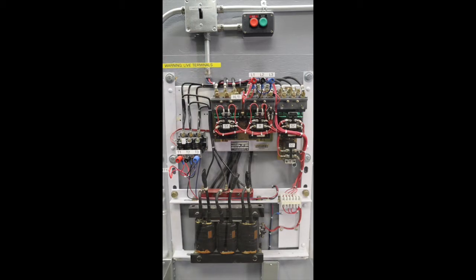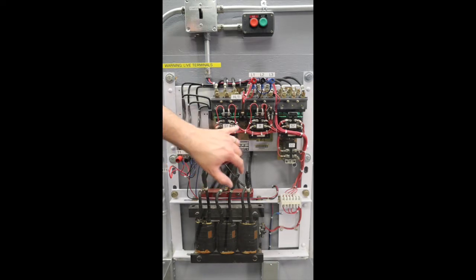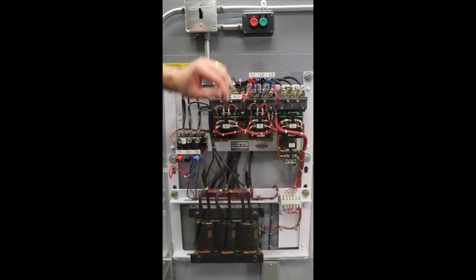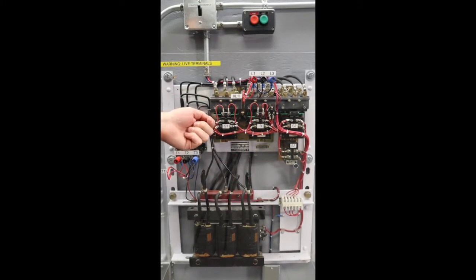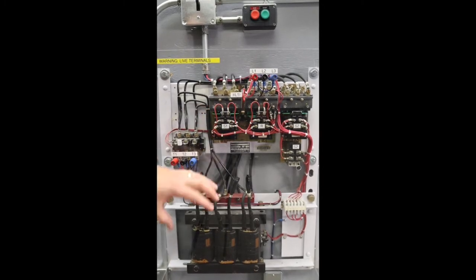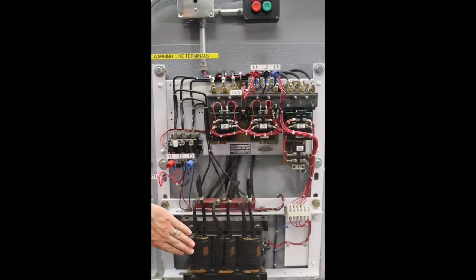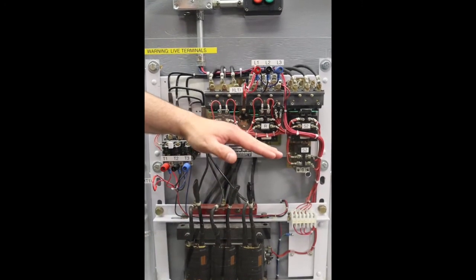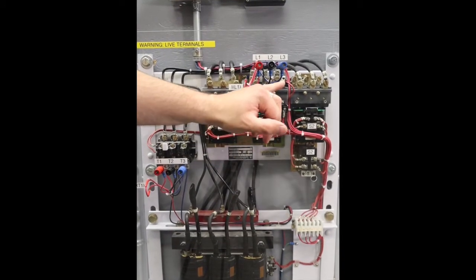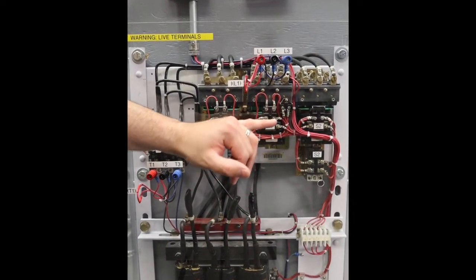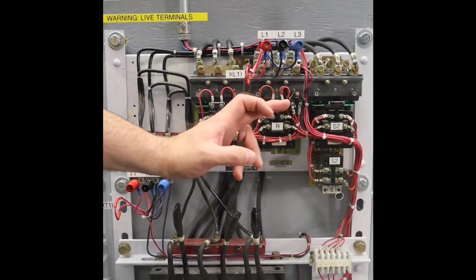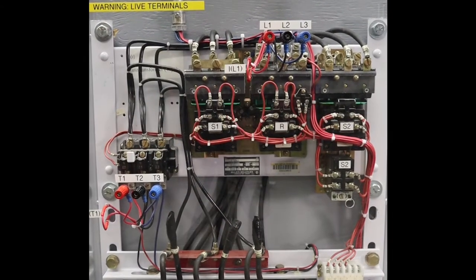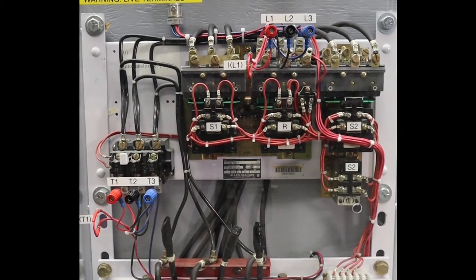With the auto transformer motor starter, what we're going to see is right when I hit that start button, my S1 and S2 coil will energize. Now what will happen in the transitioning period, S1 drops open, which opens my Y point for my auto transformer, then it's still energized through S2, only now using the auto transformer as almost an inline resistor, and you'll see it switch into R, and then S2 will open. So when it's in run, it'll be at full voltage.